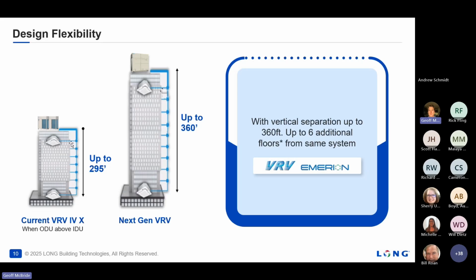We have some great vertical separation. We're seeing a lot of taller buildings that are going VRV these days. We personally have a 14-story and a 17-story multifamily building that have been built with these systems. The Aurora series goes up to 290 feet vertical separation from condensing unit to lowest fan coil, and the Emerion system goes up to 360 feet. There are some caveats and rules, but the gist is we can now service very tall buildings without having to put these condensing units in the garage, outside on grade, or even on the building itself, which is what you see a lot in Europe and Japan, or especially for mini splits where they put them all over the building. But the desire for most engineers is to put them on the roof or in the garage. And in this case, we can put most of them for very tall buildings on the roof.